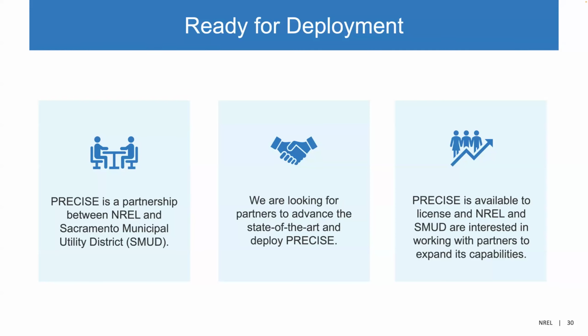Yeah, for primary protection, I think you covered it well. When we look at thermal protection, that aspect is already sort of covered with the thermal capability evaluation. But primary would hopefully be the next stage, maybe once we add that functionality to Precise, where we start looking at the primary side, but it's not there yet. The typical way for us to evaluate impact on protection would be running a load flow simulation using load flow simulation software. We use Synergi in-house here at SMUD. So that's how we would evaluate that. Great.